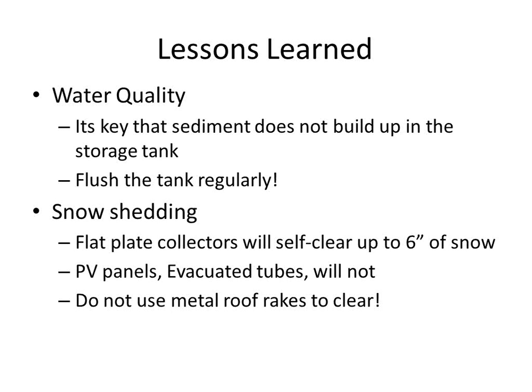What I tell people when they ask why this is true: if you flush and find you get 1 or 2 grains of sand every 6 months, you may be able to go to every year. Now, if every 6 months it has to run 15 minutes before you get clear water, you probably ought to be doing it every month. The whole goal is to make sure you're not allowing sedimentation to build up.